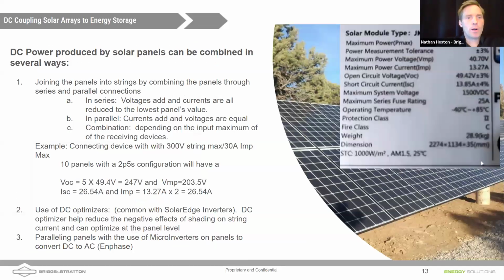Okay, DC power from solar panels can be combined in a few different ways. So we mentioned that when you have DC power sources, if you put them together in series, the voltage goes up, right? And the current is limited by the least producing panel in that series string. It's also important to keep in mind that when you string panels together in series, their voltages add together. And so when their voltages add together, you can increase them towards an upper limit.